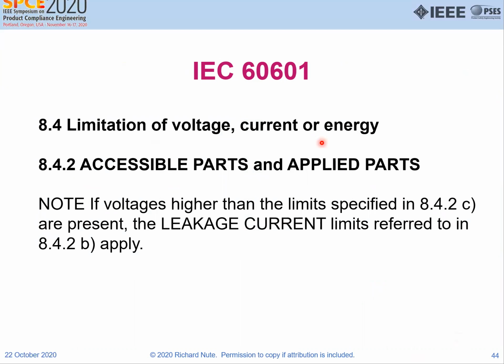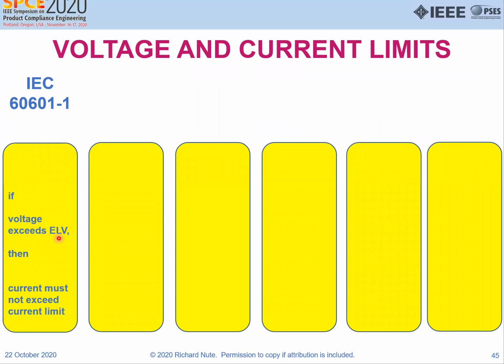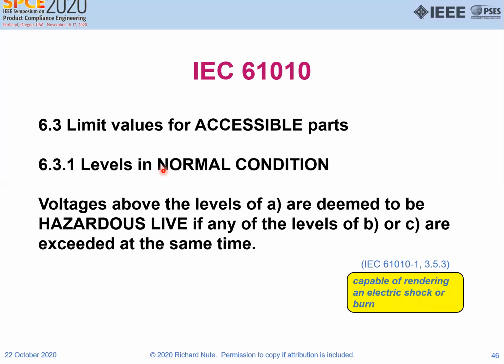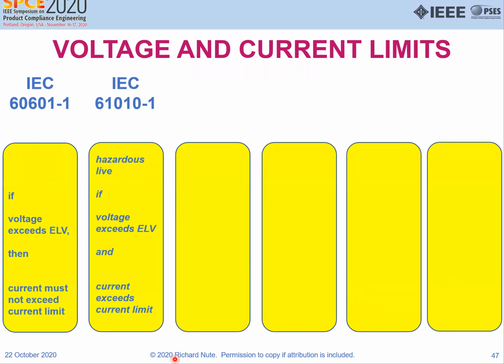The first standard, 601, is the medical standard. Limitation of voltage and current, and don't worry about energy. Accessible parts: if voltage is higher than the limits specified, don't worry about what they are, leakage current limits are referred to. So in 601, if the voltage exceeds the limit, the current must not exceed the current limit. We look at 1010 for test and measurement equipment. Limit values for accessible parts: voltages above the levels of A, ELV, are deemed hazardous live if any of the levels of B or C are exceeded. B is the touch current limit. So it's hazardous live if the voltage exceeds the limit and the current exceeds the current limit.